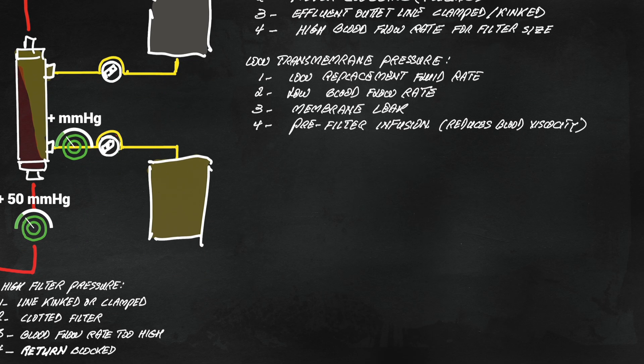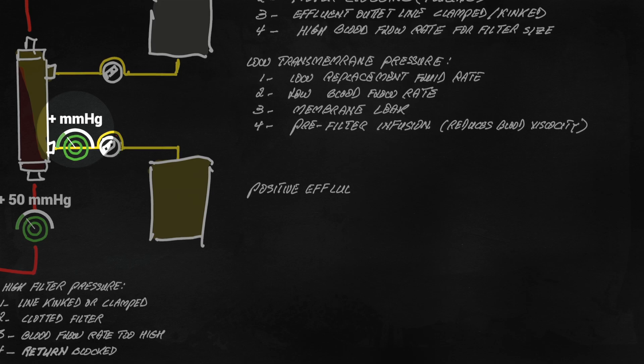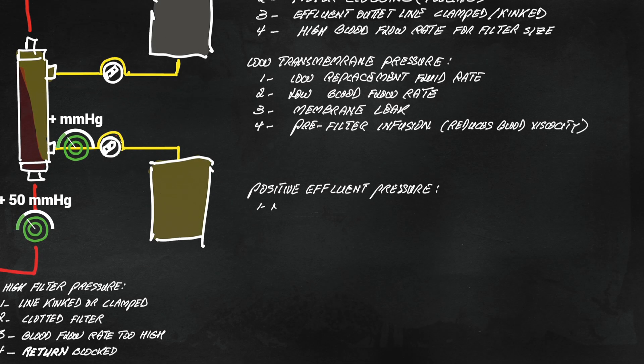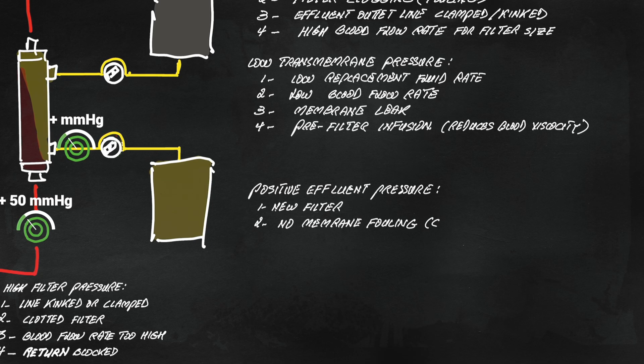Effluent pressure can be positive or negative. It is usually positive with a new membrane, which are typically high flux, meaning that they have high ultrafiltration coefficient, which in turn means that plasma water passes through easily.